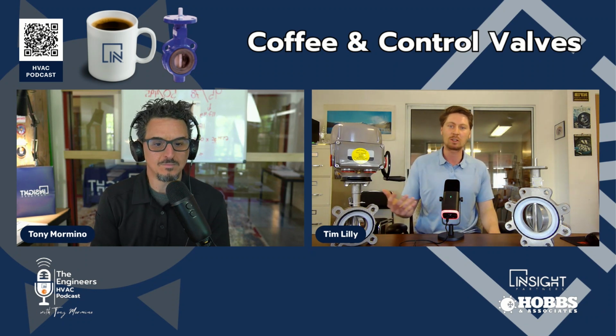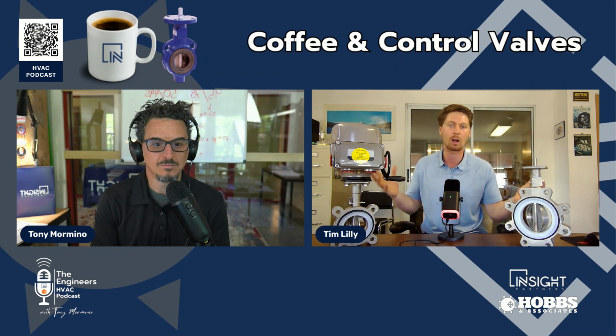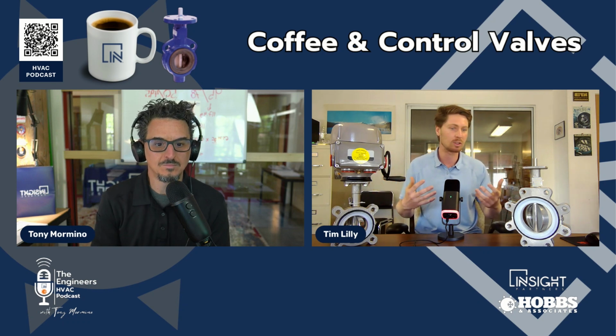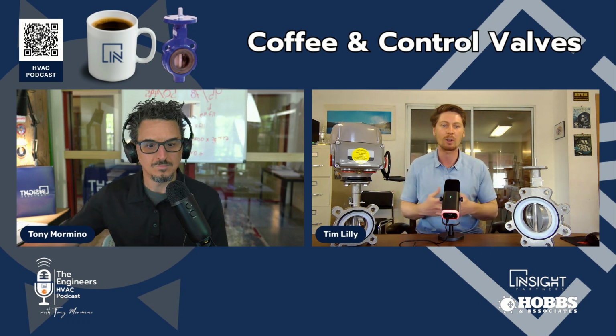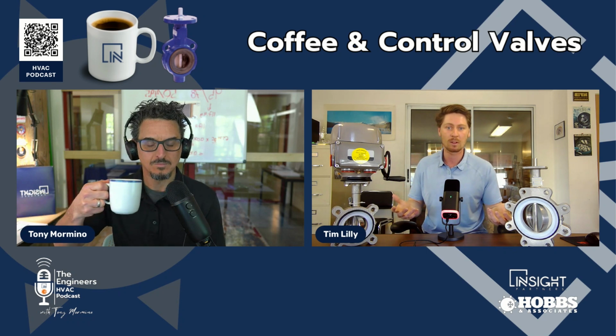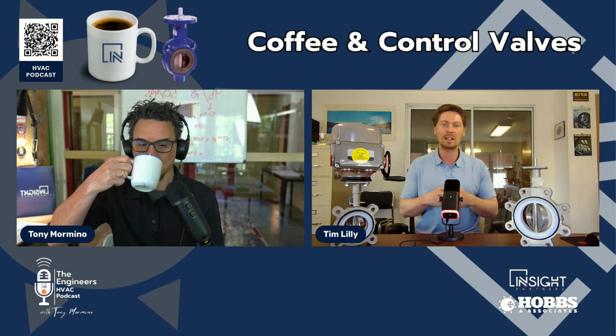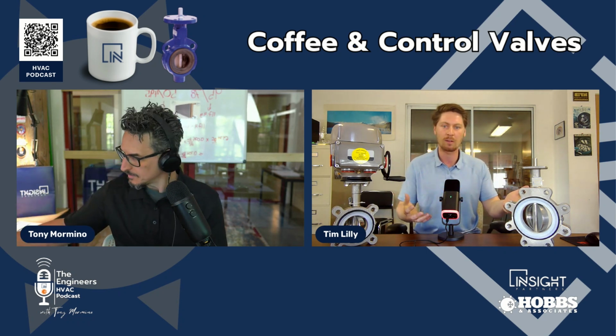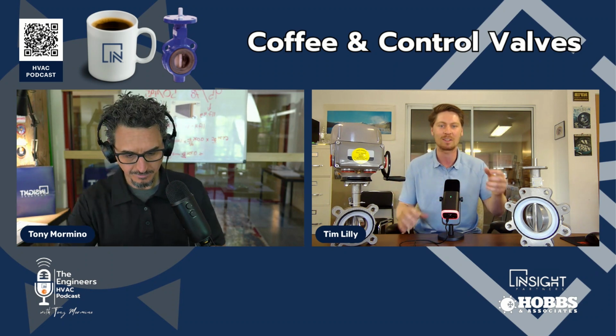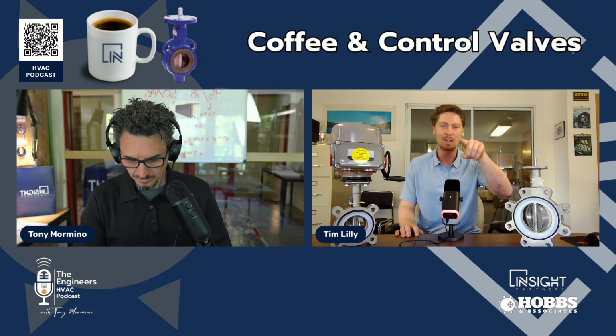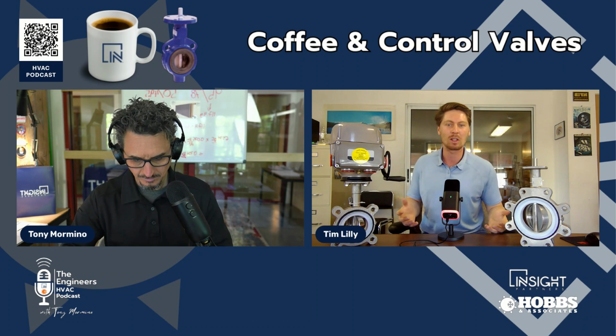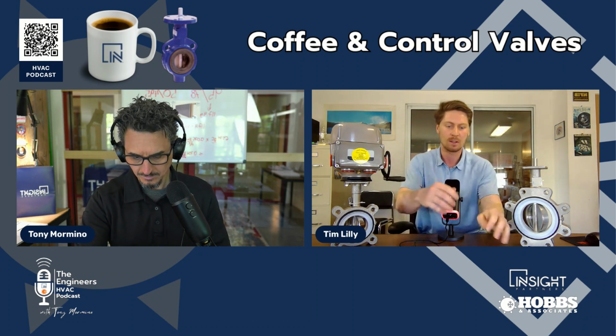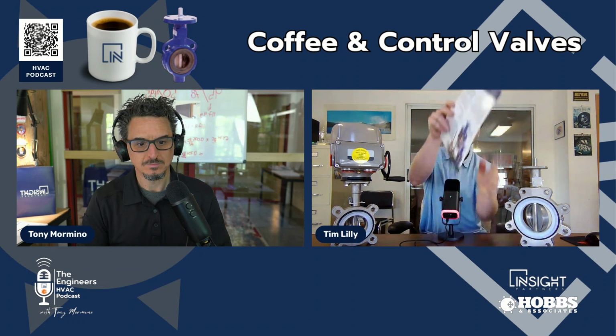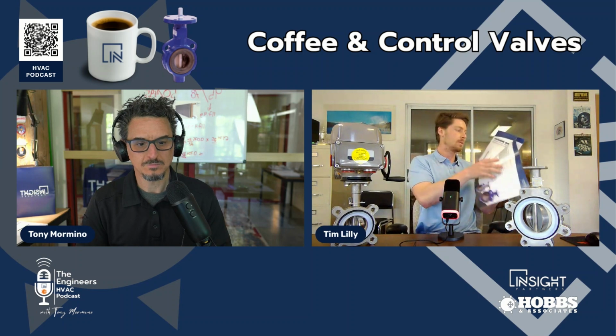And so, to answer your question, there are really kind of three main types of valves when you get into these larger, let's say, control applications. So, you have what's called a butterfly valve, a characterized ball valve, and a globe valve. And when you design a system and you go get a control valve, let's say the spec just calls for a control valve, it's that little icon with the hat on the top. What you want is what's called equal percent flow characteristics. And so that looks like this. Let me pull up a.